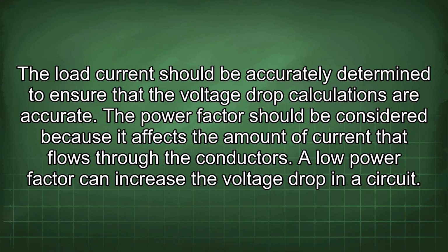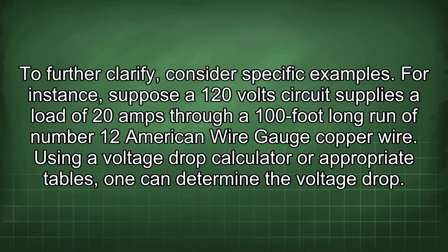The power factor should be considered because it affects the amount of current that flows through the conductors. A low power factor can increase the voltage drop in a circuit. To further clarify, consider specific examples. For instance, suppose a 120-volt circuit supplies a load of 20 amps through a 100-foot long run of number 12 American wire gauge copper wire.